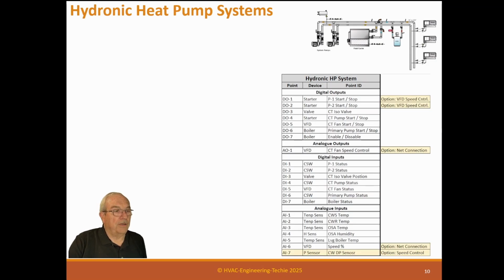Now we have heat pumps. Now, heat pumps are exactly the same as what we just looked at. It's got water-cooled heat pumps with heat exchangers in them, and we have pumps and we have a fluid cooler, but now, since these are heating, we need to have a boiler. In case it gets cold enough that these suck all the temperature out of the water, we'll need to add some temperature into it.